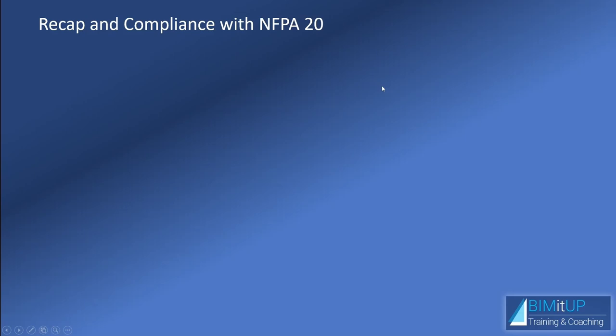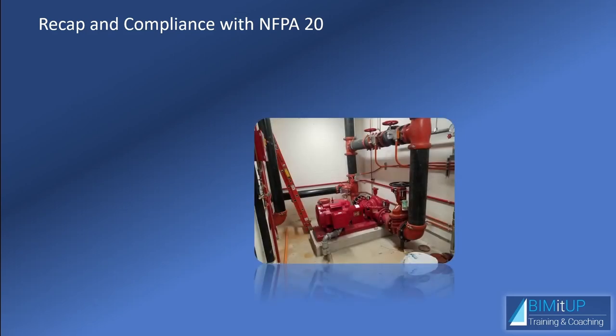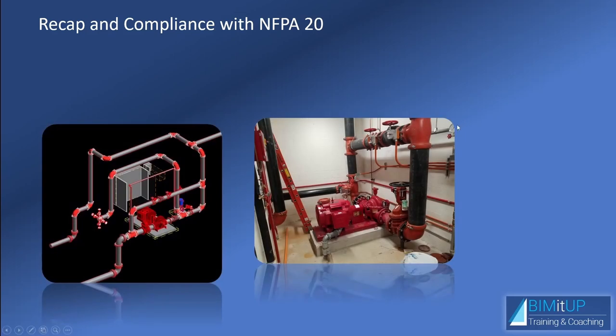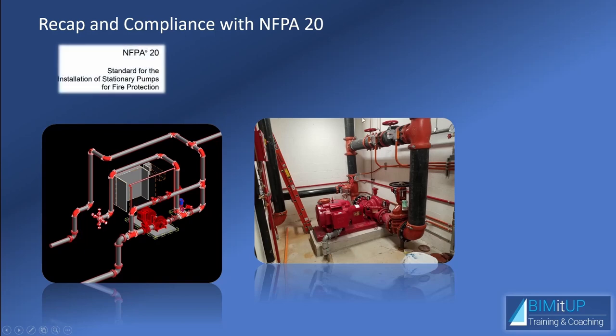Just fly through NFPA 20 compliance for the purpose of this presentation. We didn't talk about the bypass. It's a good idea also to have a bypass. It's not strictly required, but it's highly recommended. In case you need to obviously do some maintenance on your fire pump, or if for some reason your pump can't operate, at least you have city pressure water going into your system, your standpipe and your sprinklers.